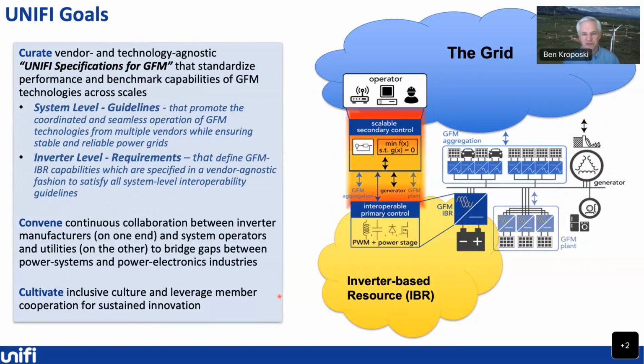If you think about what the challenge revolves around, it's how do you specify grid forming technologies such that the grid is making sure that you're providing reliable, stable operations from the grid's perspective. And then from the inverter perspective, how are you defining those interoperable requirements and interconnection requirements in a vendor agnostic way? So how do you keep the grid operator happy? How do you keep the inverter manufacturer happy with their proprietary controls? And how do you map these together? So we've been exploring a number of different ways to develop specifications around this area so that we can have controllability and interoperability across multiple vendors.